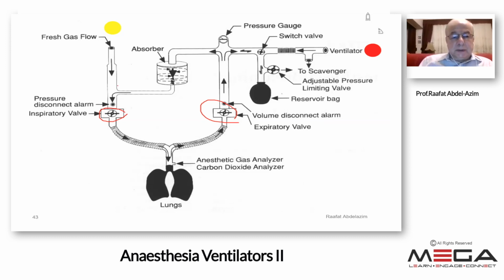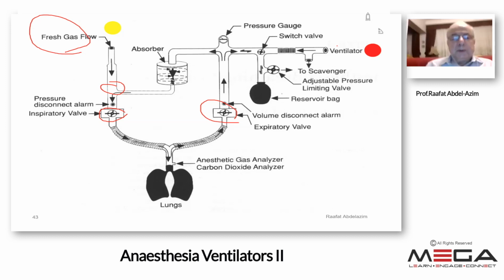At a certain point, the fresh gas flow that is coming from the flow meter into the vaporizer, coming out of the fresh gas outlet, contains oxygen and inhalation anesthetic. It will join what is coming from the ventilator, joining each other and go together into the patient's lung. If I close the fresh gas flow completely, the ventilator will not stop its function. It is going on, and the contents will not contain oxygen and inhalation anesthetic. So there will be 2 effects. These are hypoxia and awareness of the patient.